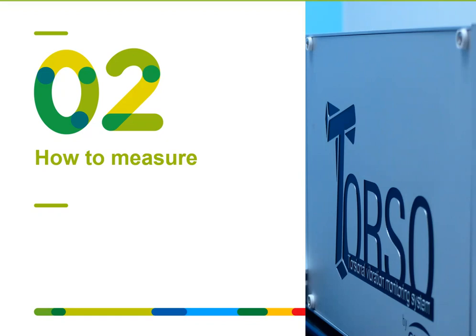The other potential issues are typically well covered in the design. These are excitation at once and twice grid frequency. So there, the norm stipulates guidelines on the exclusion zones from these frequencies. So now we step from the theoretical side more into the practical side. So how can you measure torsional vibrations?